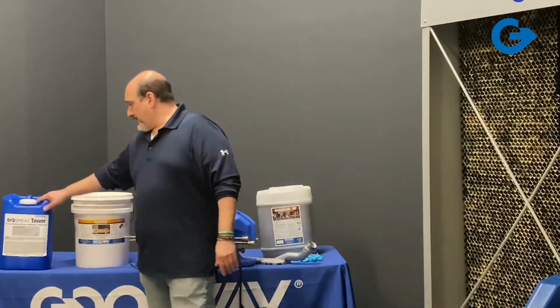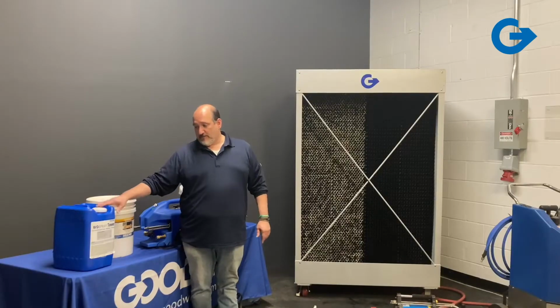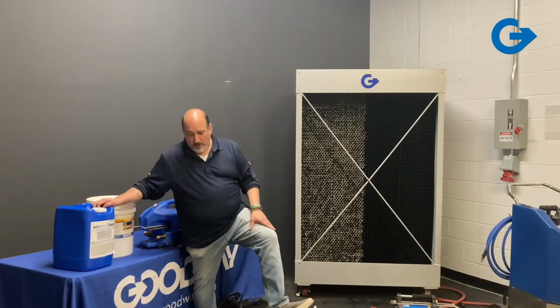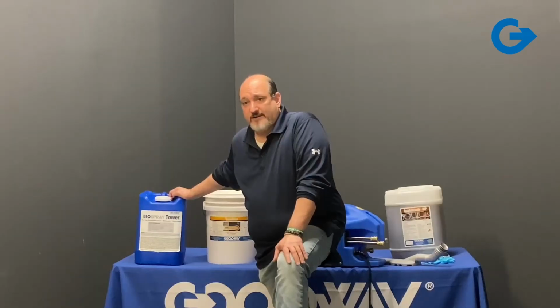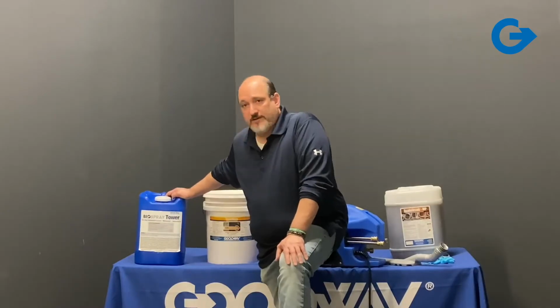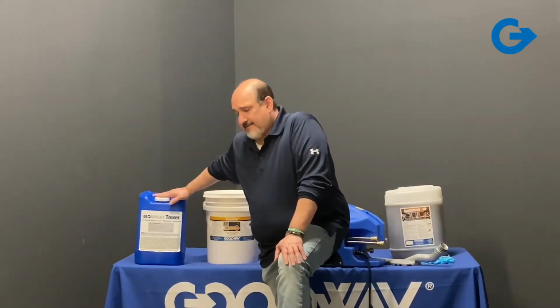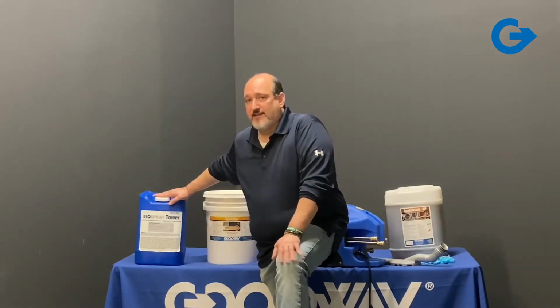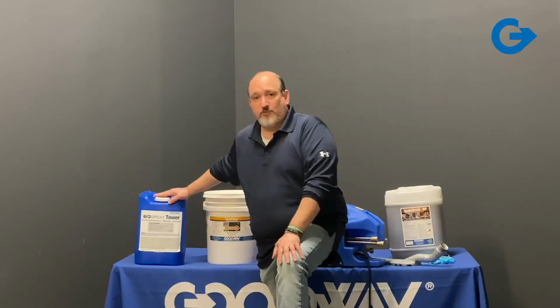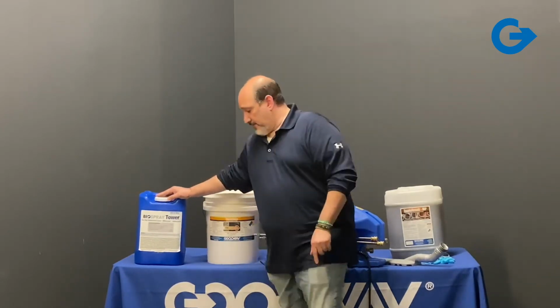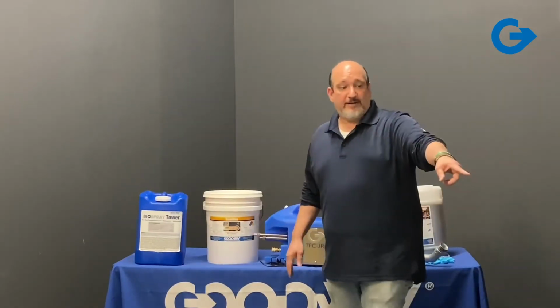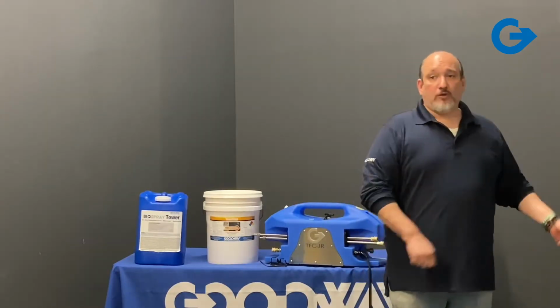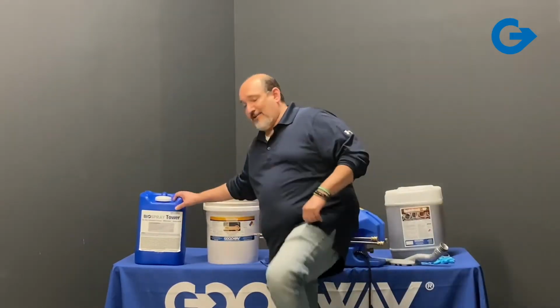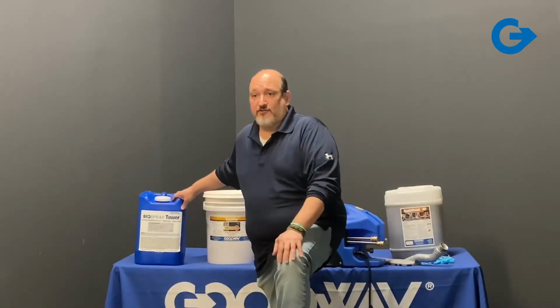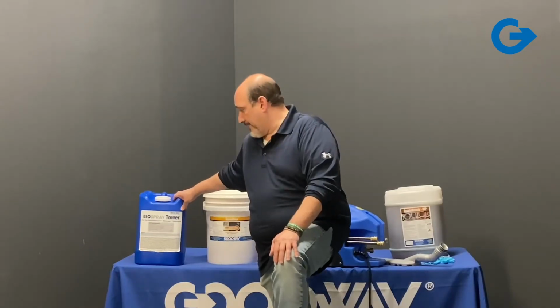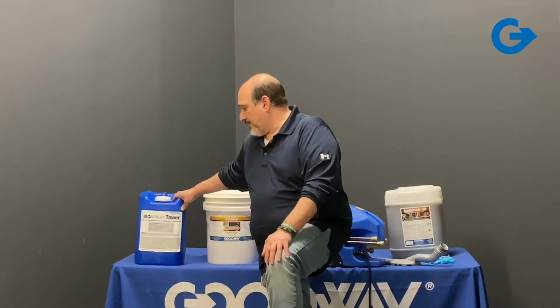Another chemical we make is a treatment applied afterward, and this one needs to be applied at 100%. It's called BioSpray Tower, a biocide for killing bacteria, including Legionella and all that good stuff. You spray it on at full strength and leave it—you're not rinsing it off. So this would be after you've completely finished everything: you could hook it up to your TFC Junior, or put it inside your TFC 200, and just spray a coating over the whole tower. Besides working really well, it also has an EPA registration for use in HVAC areas.